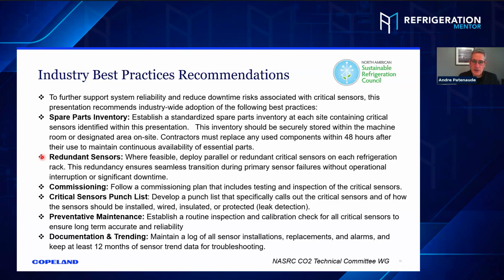Start specifying or using redundant sensors if you can, right? To your point, some guys are putting them in and they're doing that themselves. Commissioning, and you mentioned that earlier, make sure your commissioning is done right. You check, you validate every sensor before you start, especially those critical sensors. They will take you down right on startup. So you don't want that. Critical punch list of those sensors, preventative maintenance, double check the calibration when you go in there. You're not checking 800 sensors. There's only 8 that we're talking about that you need to make sure are properly functioning, to give yourself a chance or your retailer a chance, and document logs and trendings of all that stuff.